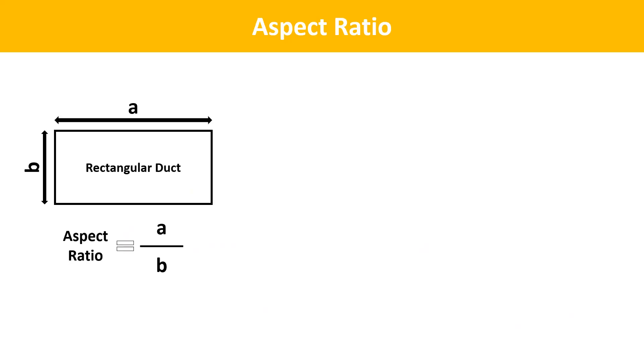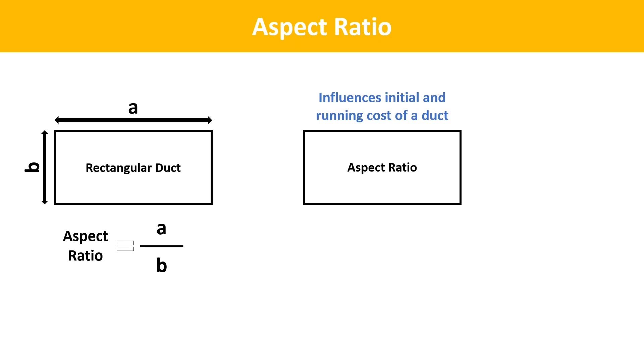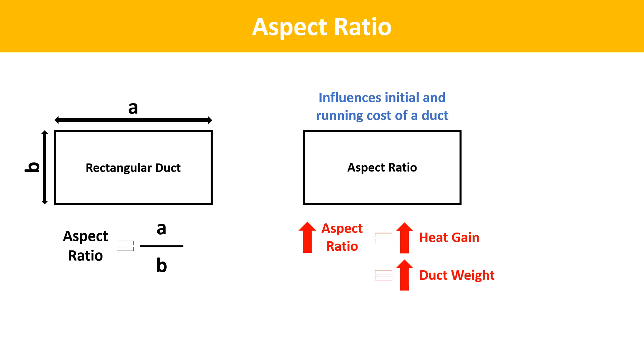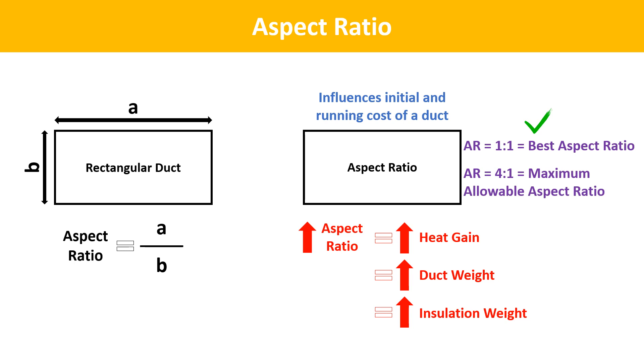The next term is Aspect Ratio. It is defined as the ratio of the long side to the short side of a rectangular duct. Aspect ratio is a major factor which influences the initial and running cost of a duct. As it increases, the heat gain by the duct also increases. If aspect ratio increases for a fixed duct area and capacity, the weight of duct material and weight of insulation also increases.